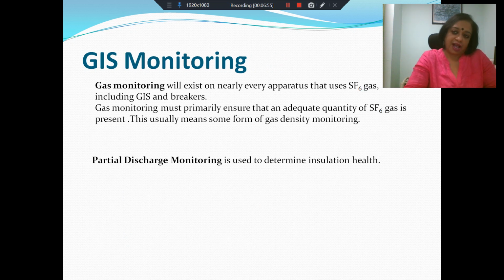So GIS monitoring has to be done very carefully, because everything is prefabricated and enclosed, and we don't even feel the need to do any servicing or maintenance over the initial periods. We have to make sure that monitoring is done. The most important GIS monitoring is the monitoring of the gas. The first thing we need to make sure is that there is always enough gas inside the enclosure, so that the dielectric breakdown strength we are counting upon and the arc quenching capabilities are available. So enough gas has to be there. That's the first thing that has to be ensured, and for that, we have some kind of gas density monitoring.